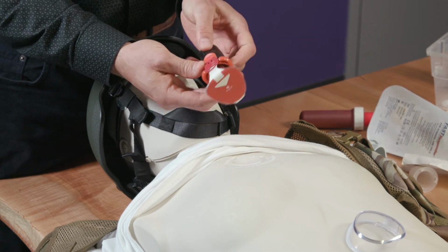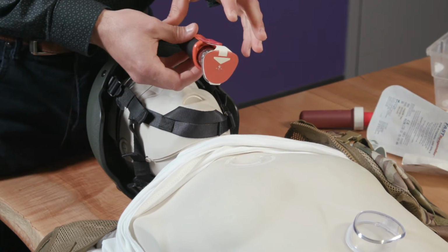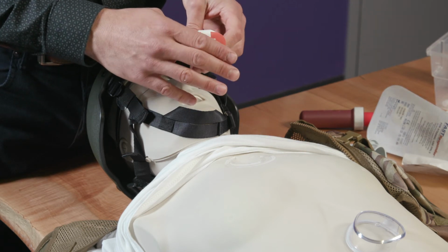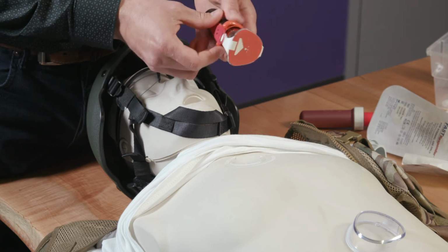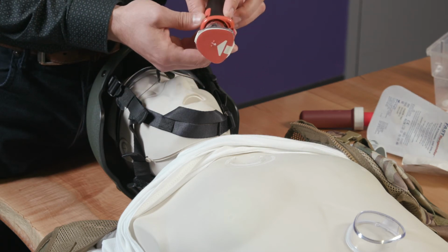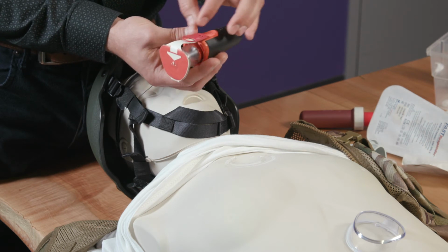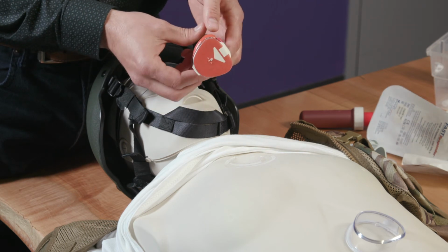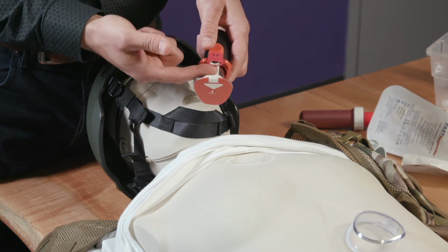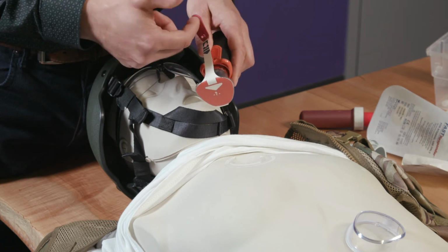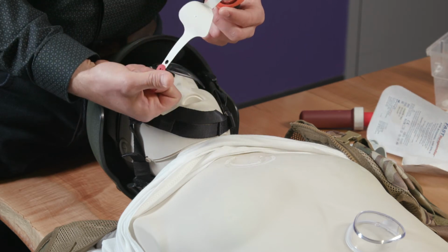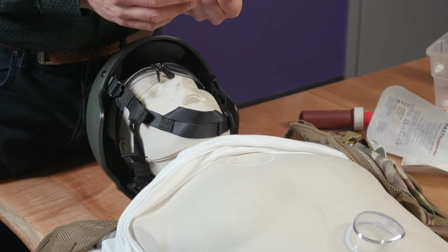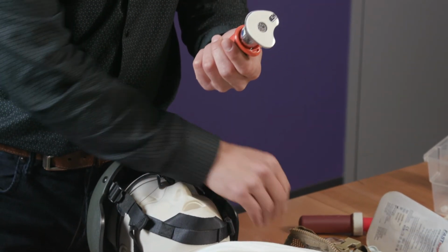This is the device that we came up with. The device has a lot of features integrated into it that used to not be: sharps protection, an integrated foot, and the safety. Everything is integrated into one piece. We made it smaller and lighter and simpler to manufacture. As well as thinking of the usability, we also had to think about the manufacturing side of things. Then you take this tab off, and what the tab does is peel the label off the bottom, so it's now sticky, and then you just give it a tug, and you're left with a device ready for activation.